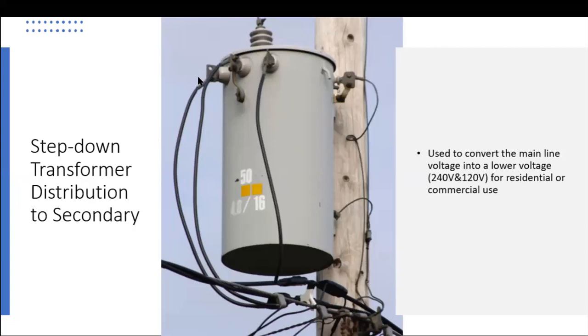Step-down transformer. Well, above here, we're at our distribution voltages, and we used 7,200 a lot before. But now I need to get it to a voltage where I'm able to bring it into my home. So I've got to have one more transformation process. This transformer is used to convert the main line voltage or distribution voltage into a lower voltage, 240 and 120, for residential and commercial use.